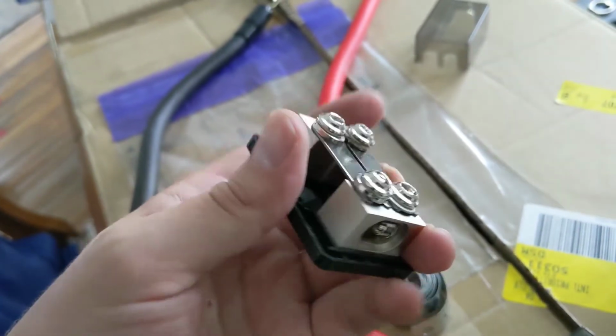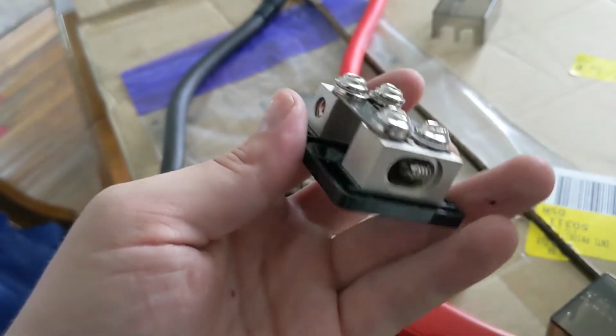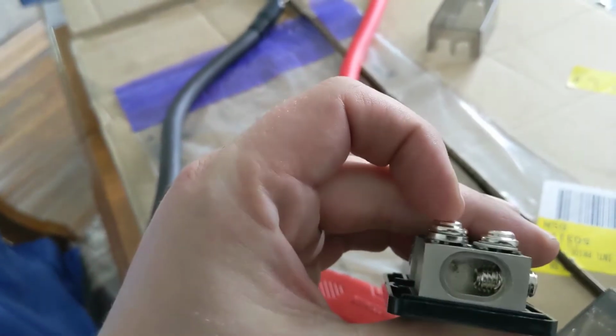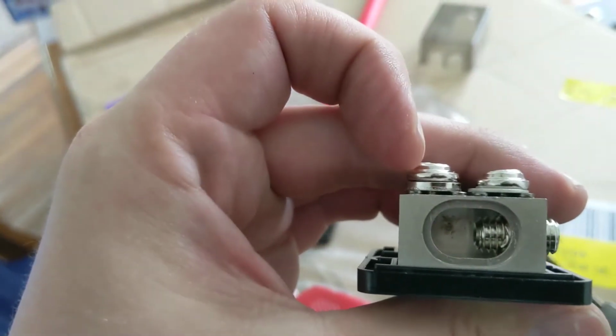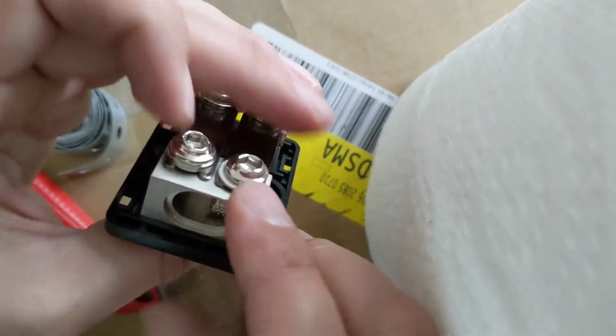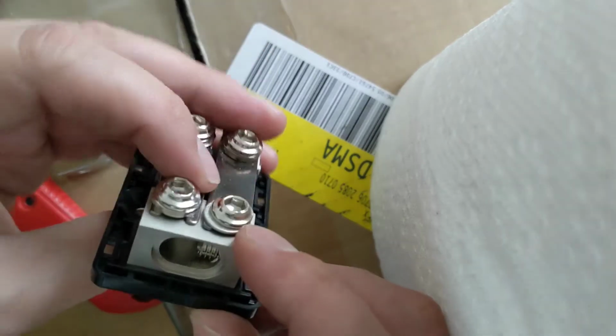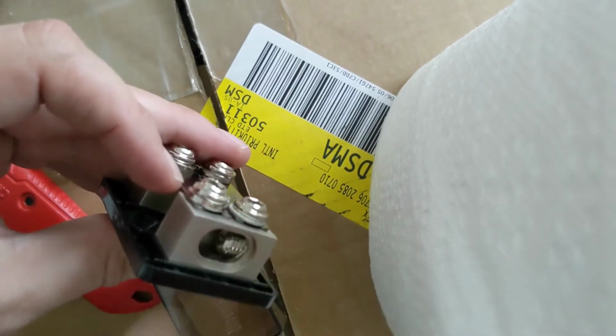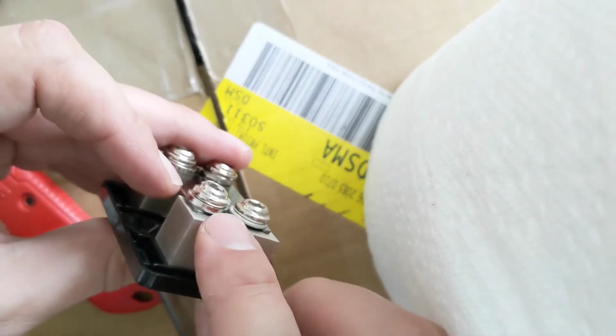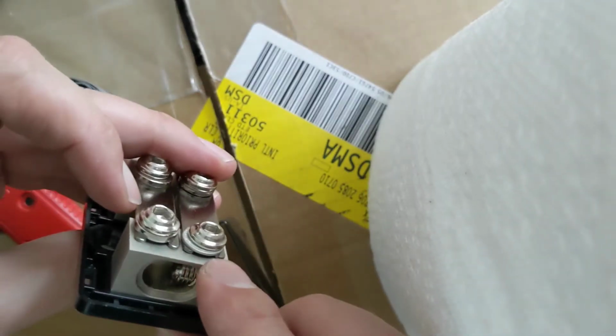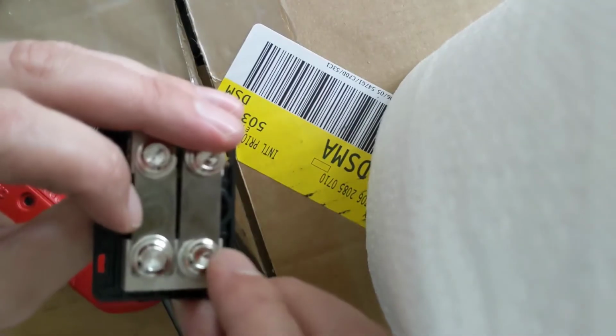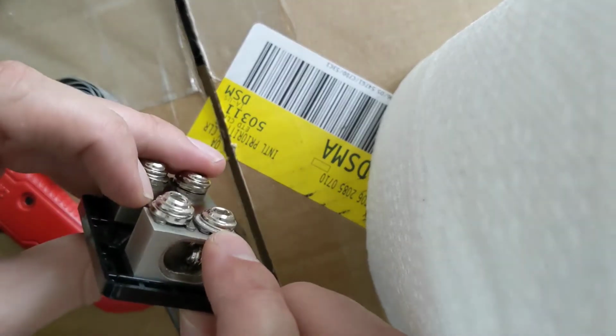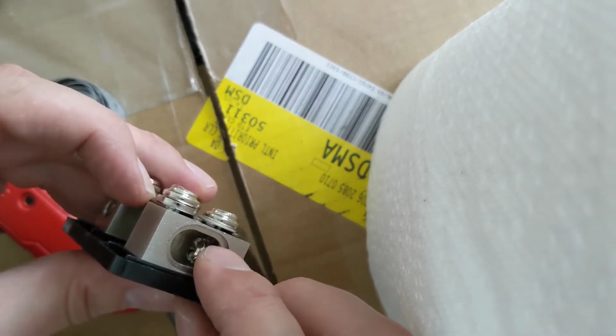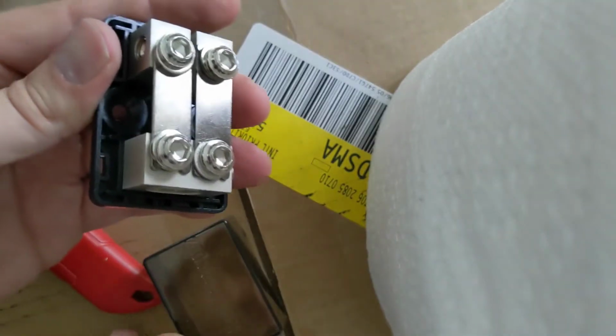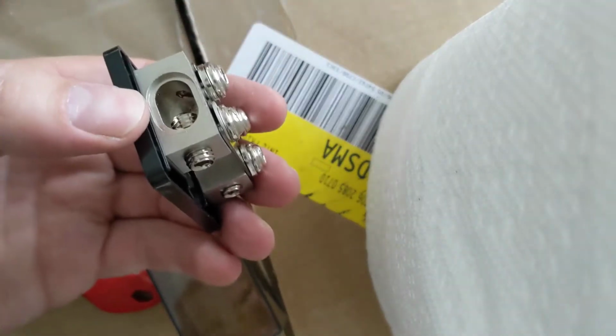A word of caution with these fused distribution blocks: the thread on these bolts is super small, I don't know if you can see it in there. This one actually stripped out with almost no effort at all. So I removed the thick washer that came with the setup. You can see the thick washer here. I took a blue ring terminal, cut the circular head off of it, and used that thinner washer instead so I could get down to some good threads. But be careful with these things, that one stripped out way easier than I expected.